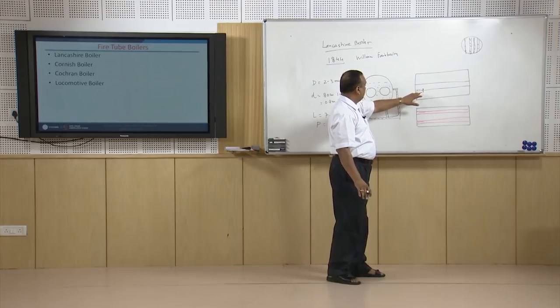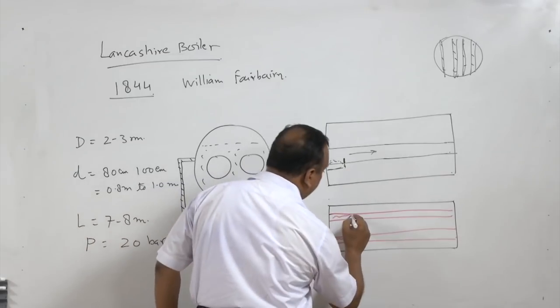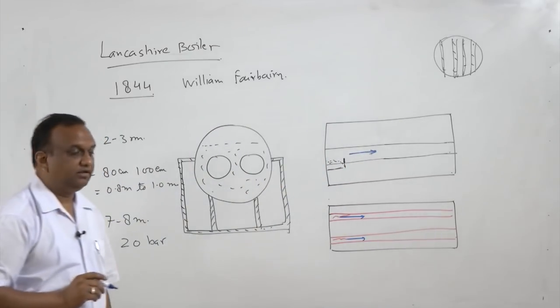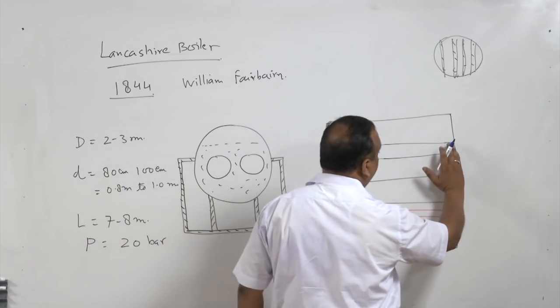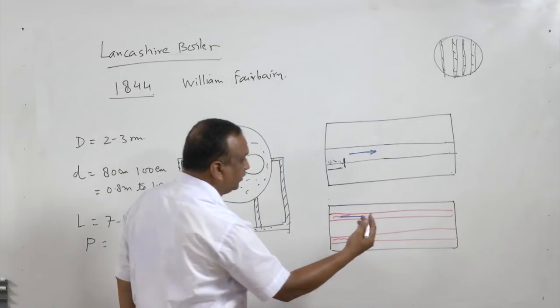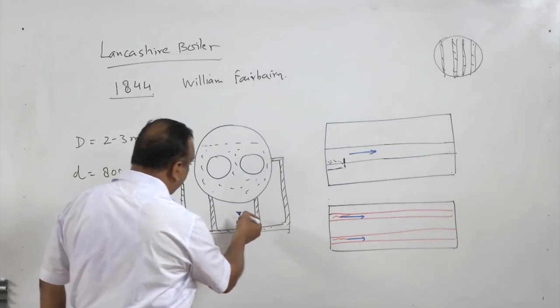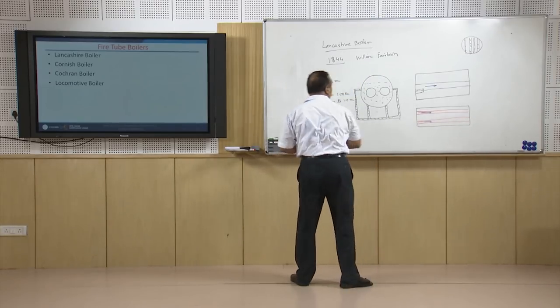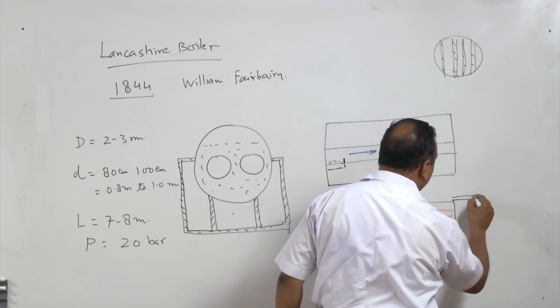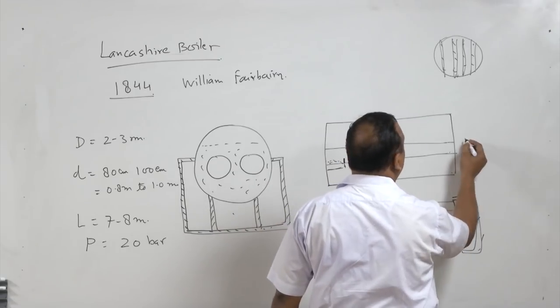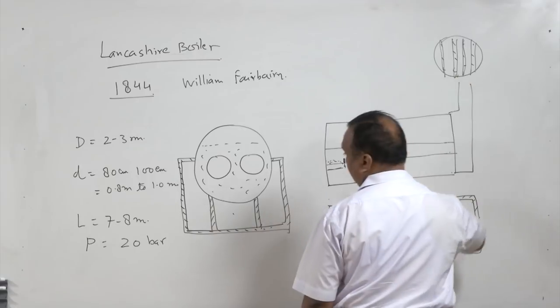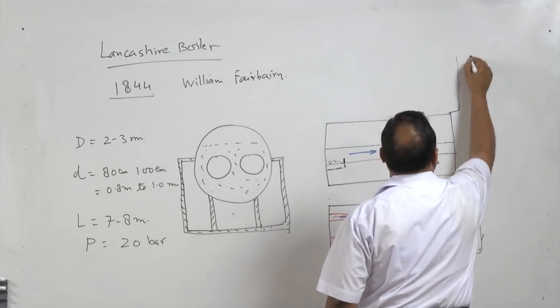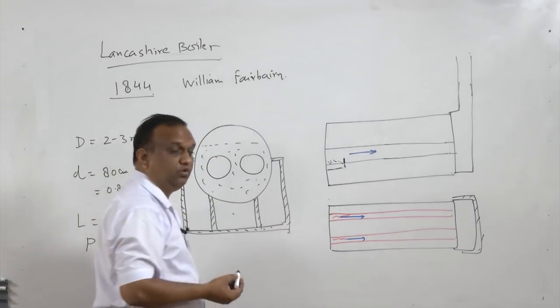Fuel is burnt here and the flue gases move in this direction through both tubes. From the top the flue gases move in this direction, and at the end they take a U-turn. From the elevation they take a U-turn and emerge from the bottom. There is a flue passage for the flue gases and from the elevation there is a chimney to remove the flue gases. There is natural circulation — no fan is used in these boilers.